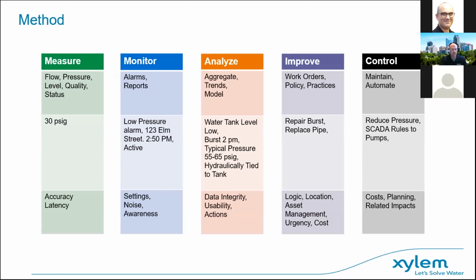You don't always need to monitor all the data — you might need to monitor the alarms or look at reports, which become time-stamped. Then, if you get enough of that data, you begin to aggregate it and bring in other information, look at trends or models to know if there's time to take action. For example, if you had a low pressure alarm at a specific location, and also learned there was a burst nearby that was hydraulically tied to that tank, you'd begin to understand the impact and where the source of the problem is.